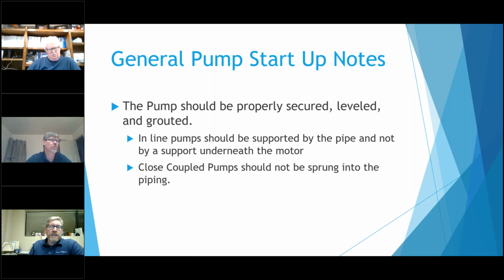The other thing I touched on a little bit earlier, closed coupled pumps, they should not be sprung in the piping. You should be able to pull the whole pump out, whether that's an inline pump or the base mounted or the end suction pump. You should be able to pull them out where the volute doesn't move or the pipe doesn't move when it's being pulled out. Eventually it just adds too much stress to the pump, and something will eventually crack. It's usually the volute that will end up cracking. So we want to make sure it's just not sprung in there.